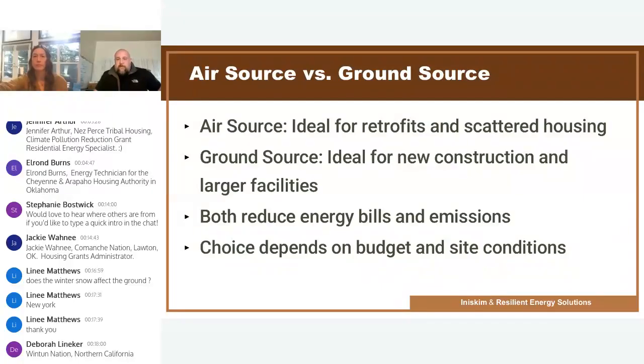The higher install cost may fit the tribe if you have trenching in-house or with a local contractor. This is typically best suited prior to new construction, or if there's a large parcel of undeveloped land adjacent to the facility. I say facility instead of house because the cost of these systems often eliminates residential applications - though not always, I'd suspect the only way you'd do ground source with a house is with grant funding to support it, since it would be difficult to make that pencil otherwise. Really, the choice between the two comes down to budget, your situation, and your long-term goals.